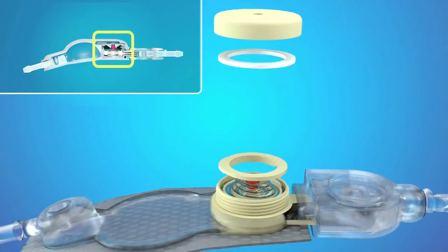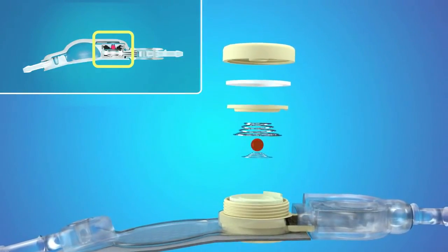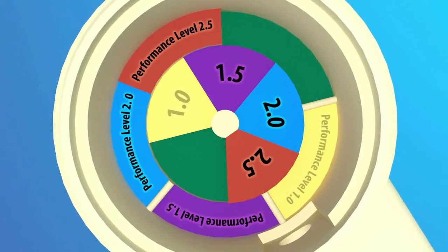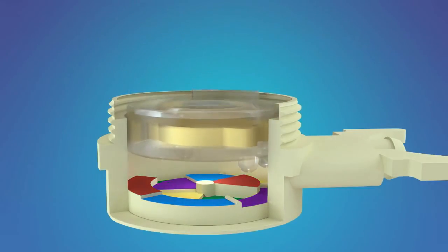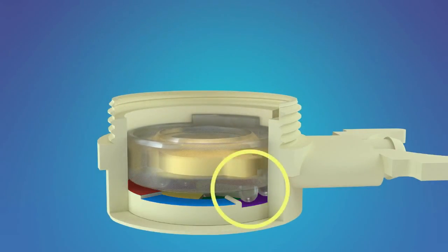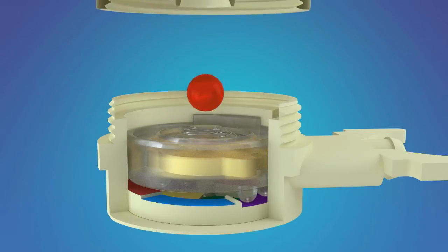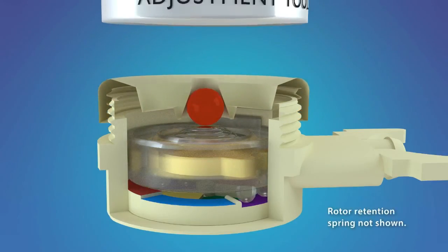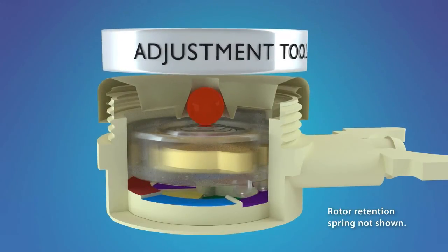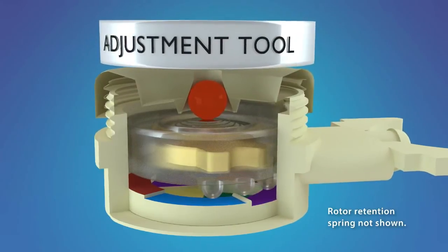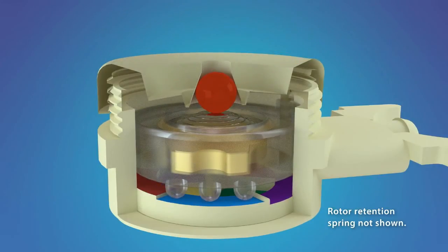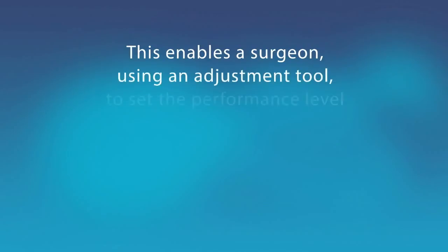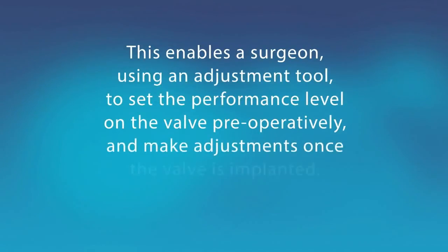The valve mechanism consists of a ruby ball and circular spring design. At the base of the valve mechanism, there are five concentric platforms of various heights. On top of the valve mechanism base is a plastic rotor element which contains a magnet. The rotor element has feet that are designed to engage with a platform stop. Mounted on top of the rotor element is a pressure flow spring which applies pressure onto a ruby ball. The platform design at the base of the valve mechanism requires the rotor to be magnetically raised onto a higher or lower platform through the use of a Medtronic adjustment tool. This enables a surgeon, using an adjustment tool, to set the performance level on the valve preoperatively and make adjustments once the valve is implanted.